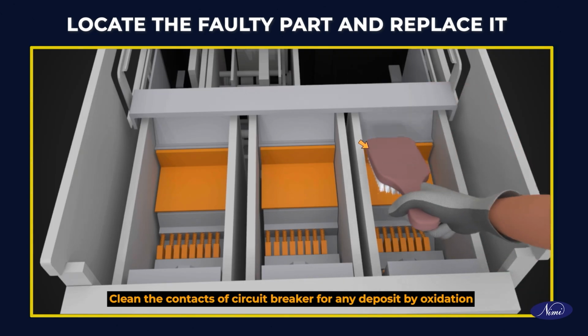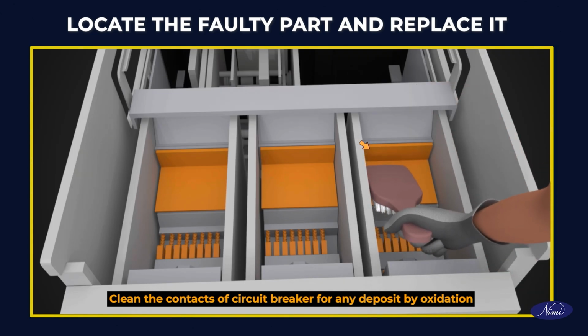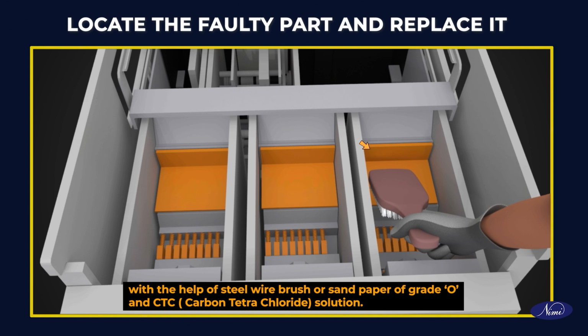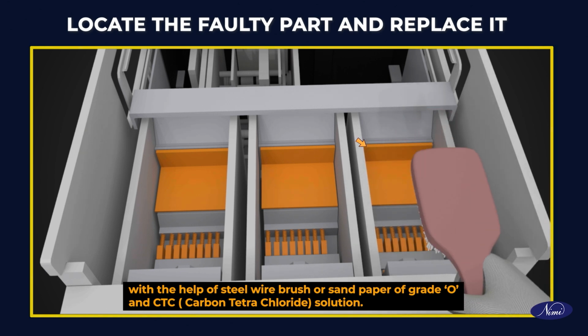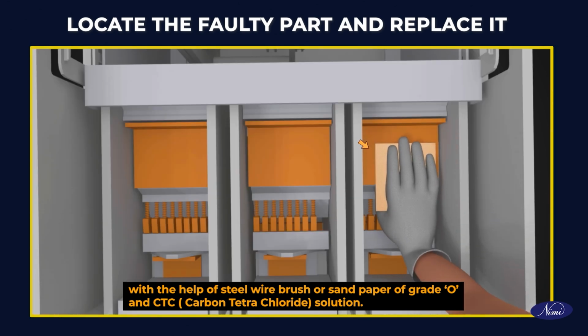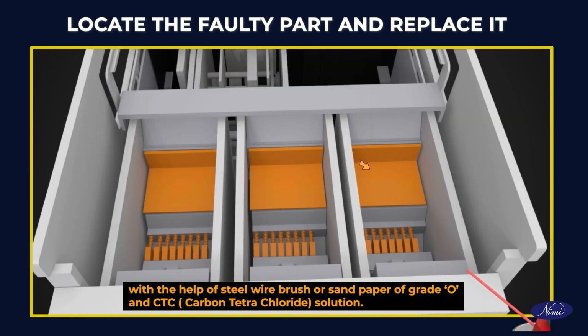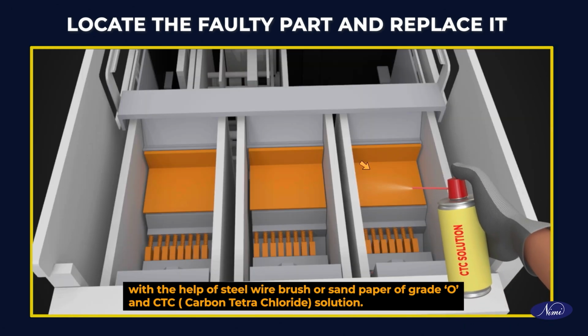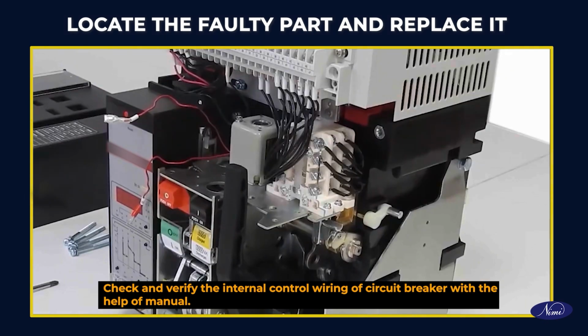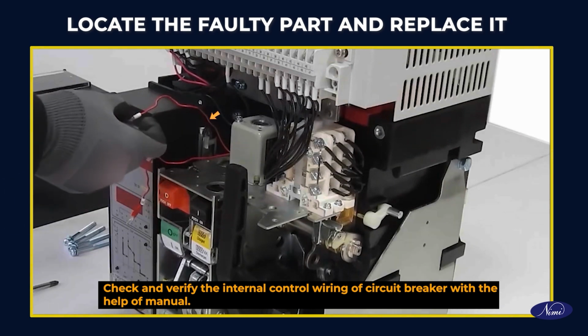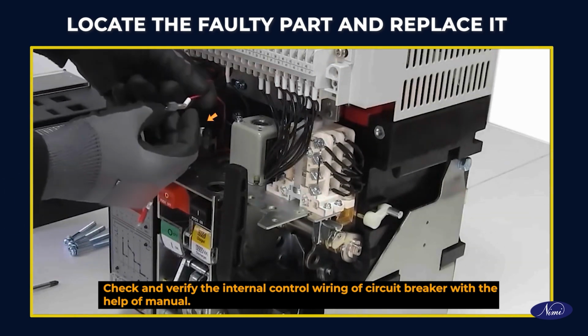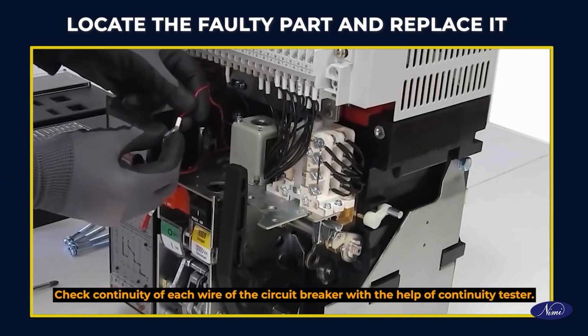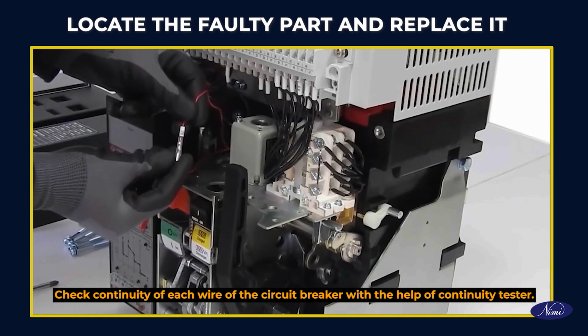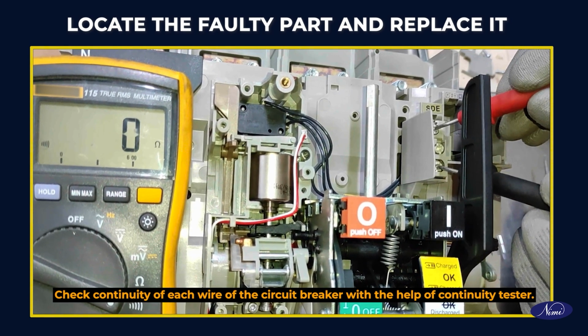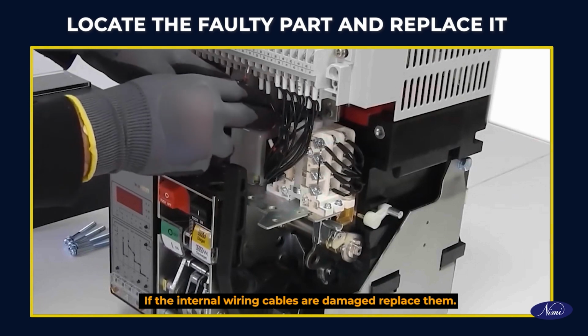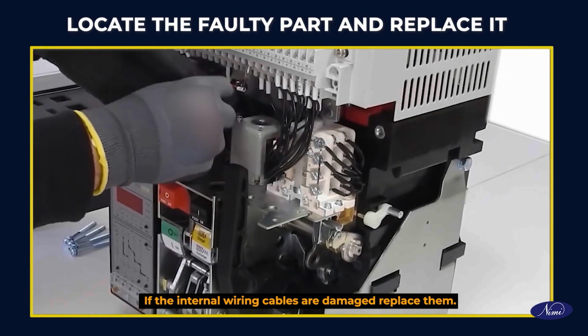Clean the contacts of circuit breaker for any deposit by oxidation with the help of steel wire brush or sandpaper of grade 0 and CTC solution. Check and verify the internal control wiring of circuit breaker with the help of manual. Check continuity of each wire of the circuit breaker with the help of continuity tester. If the internal wiring cables are damaged, replace them.